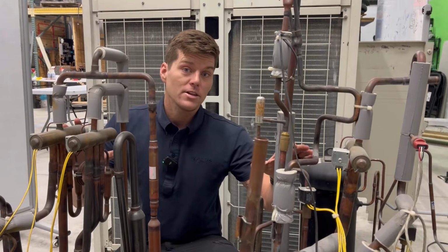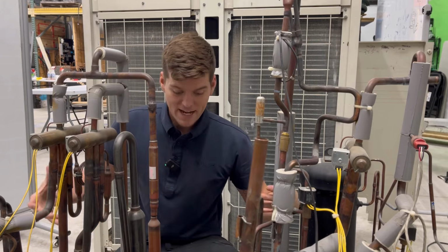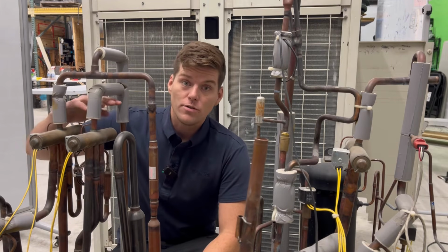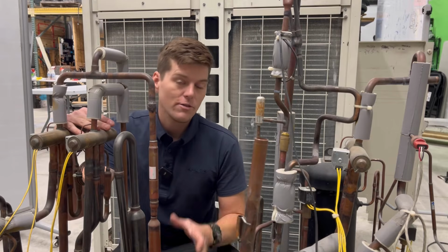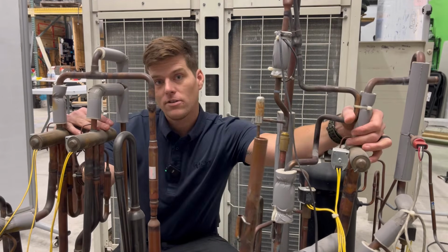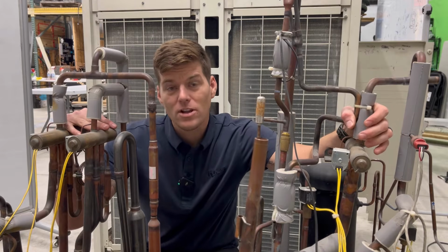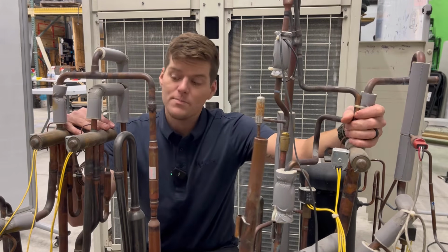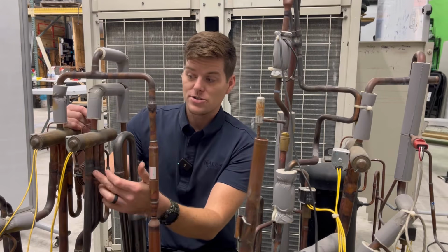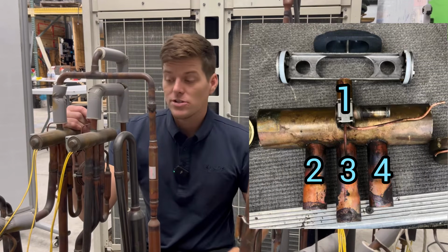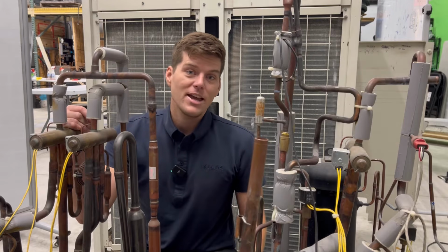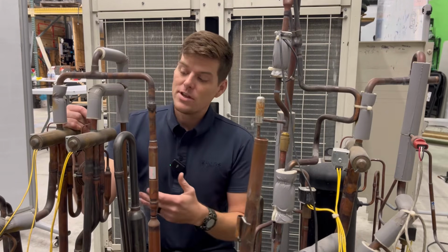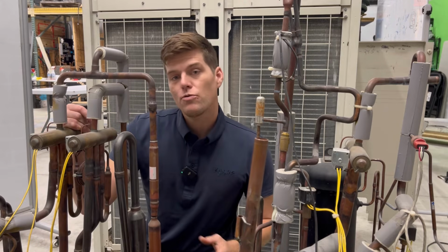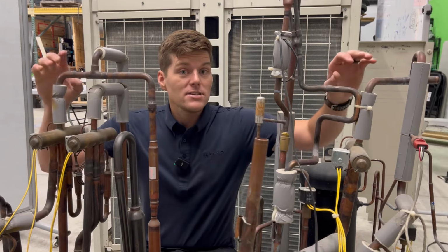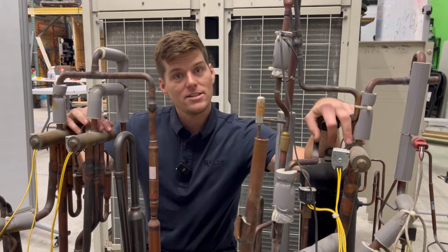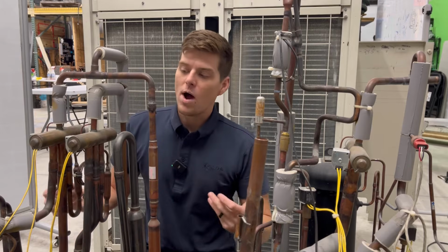Notice here that on this particular model, the one that we just looked at behind me, when we take everything apart and you actually get to the valves, there are two four-way valves on my right-hand side, or if you're looking at the unit on the left-hand side, and only one here on the left-hand side. You're going to find with VRV and VRF equipment, there are a lot of four-way valves. Why do we call them four-way valves? Well, when you look at the actual valve, you'll notice here we have three connections on the bottom, one on the top. Four separate connections on this four-way valve. You'll find that in residential applications, you get used to calling it a reversing valve. Well, for this, it doesn't really reverse the flow of refrigerant, more so redirect it to some other part of the system. Now, because this is heat recovery and not heat pump, we have three sets of valves on this one particular outdoor cabinet. And why is that?